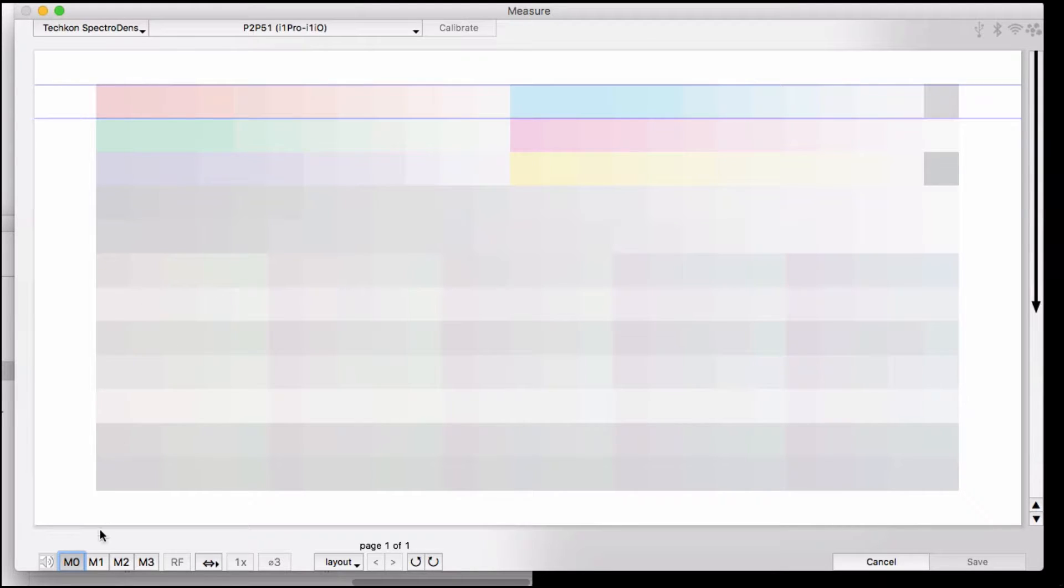The bottom of the screen lists the measurement parameters that are available to you. The SpectroDens can do all four measurement modes, including M3. Clicking the buttons at the bottom, you can usually hear the filters change in the instrument at the same time.